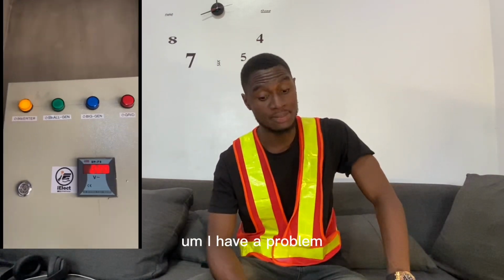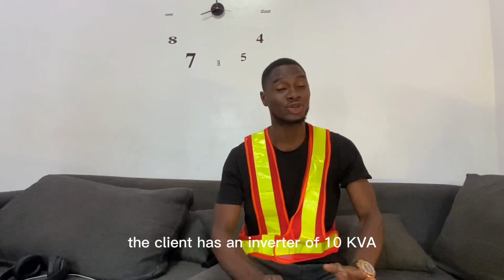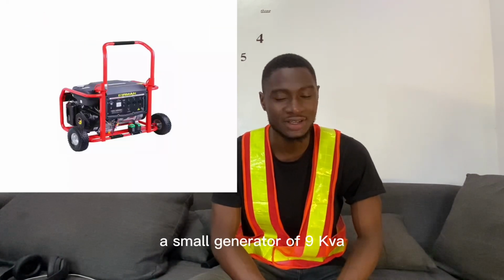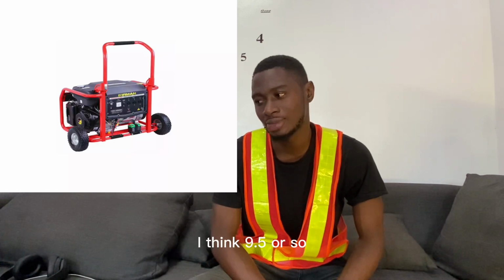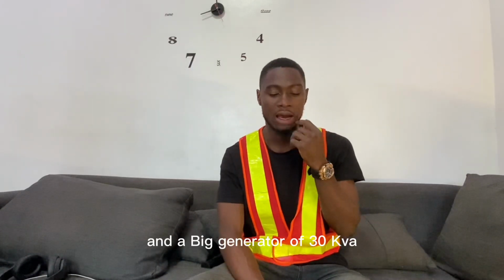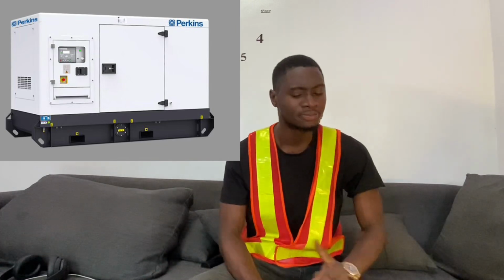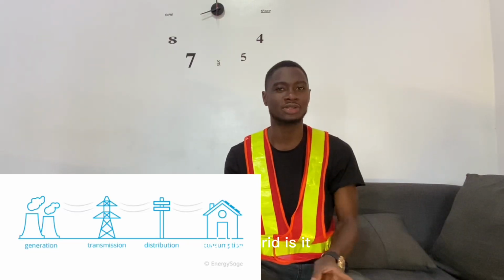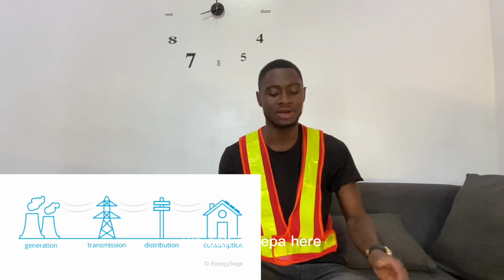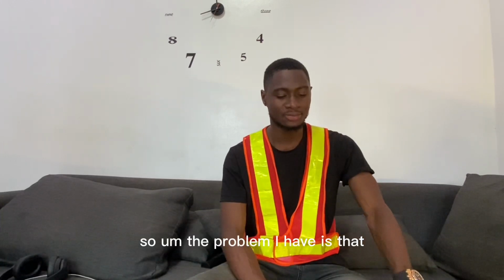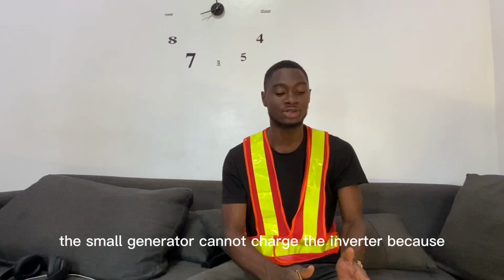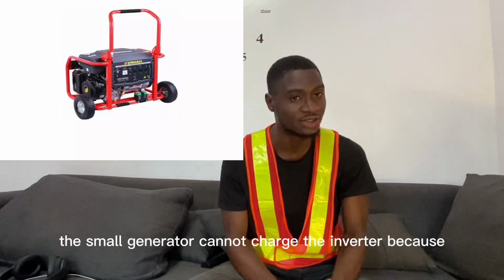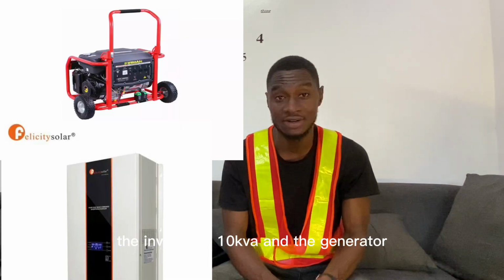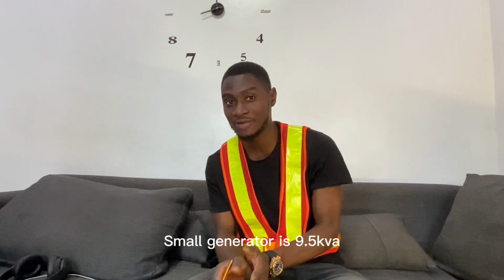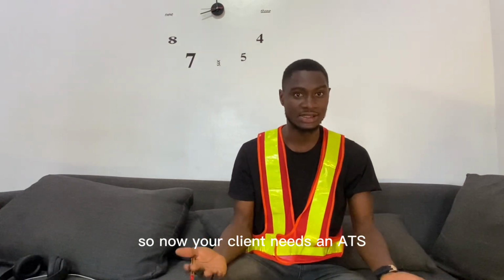I have a problem. The client has an inverter of 10 kVA, a small generator of 9 kVA, I think 9.5 or so, a big generator of 30 kVA, and the grid line, which we call NEPA here. The problem is that the small generator cannot charge the inverter, because the inverter is 10 kVA and the small generator is 9.5 kVA. So now the client needs an ATS.